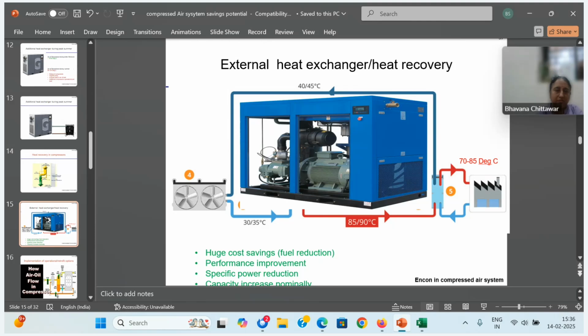So as with the Kirloskar, we will carry out performance testing only in favorable ambient conditions, because it will give more capacity during night time or early morning. One more thing I'll tell you. Whenever oil is replaced with new oil, your capacity will go down by 5 to 10%. You can check. With the old oil, because viscosity is more, sealing will be very perfect. Your capacity will be more.